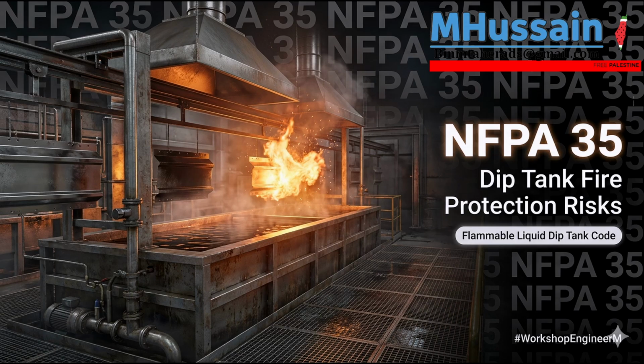If an HVAC engineer designs a beautiful system with exhaust registers way up on the 20-foot ceiling, they are just exchanging clean air while leaving the explosive hazard completely untouched down on the floor. You have to physically sweep the floor with the ventilation system. And obviously you have to pull fresh air in to replace what you're exhausting.